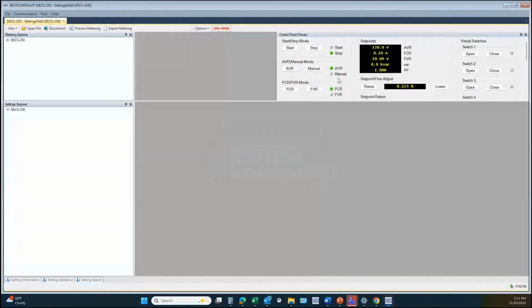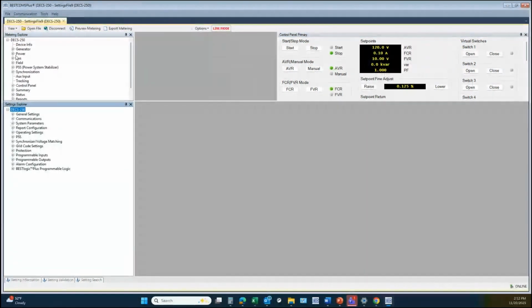As you can see, when it communicates with the DECS 250, it looks much like this. It will open up the software with a metering explorer section along the top portion and the settings explorer section along the bottom portion. Also to note is that the metering portion has the control panel that automatically pops up, and the software is letting us know that it's in live mode by default. If we expand the menu trees for either the metering or the settings explorer, we see further options available.